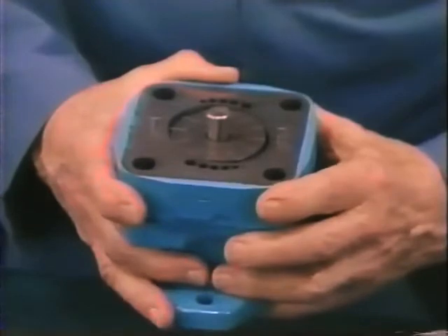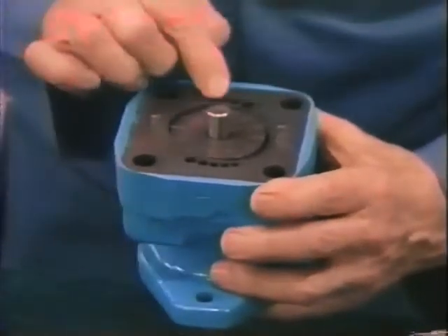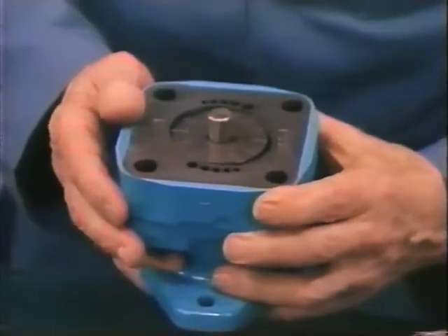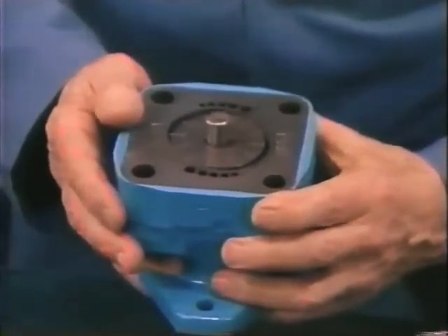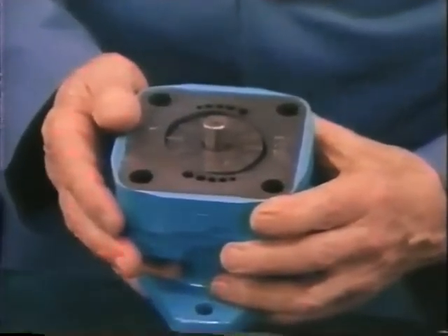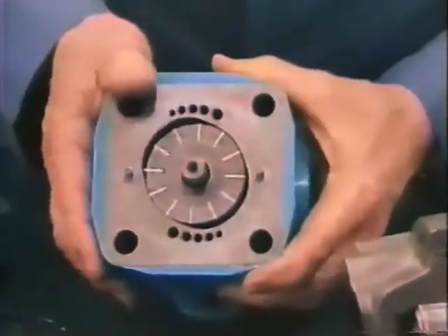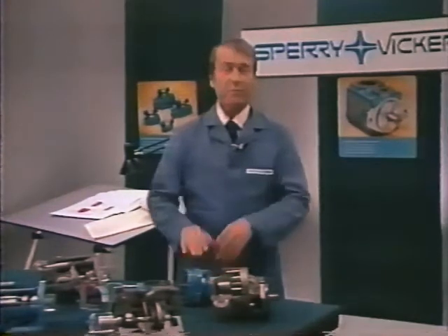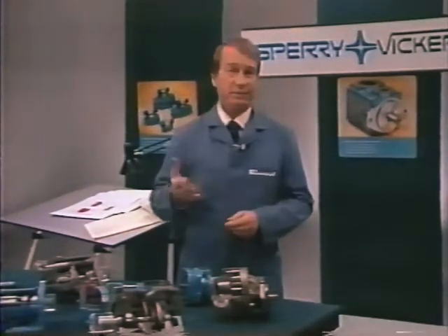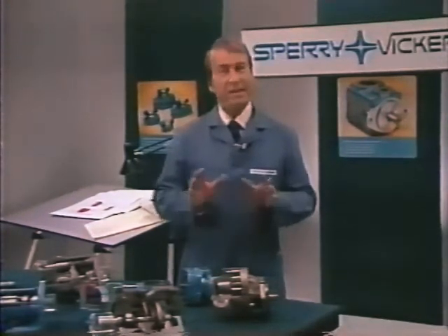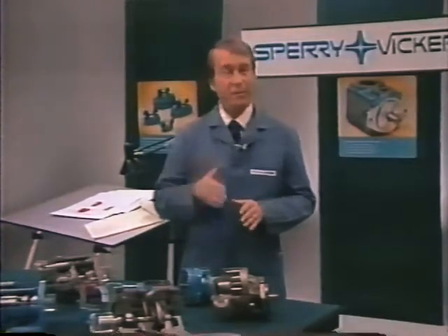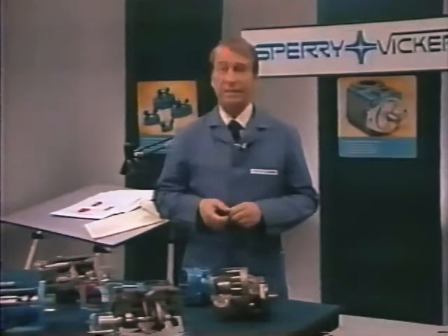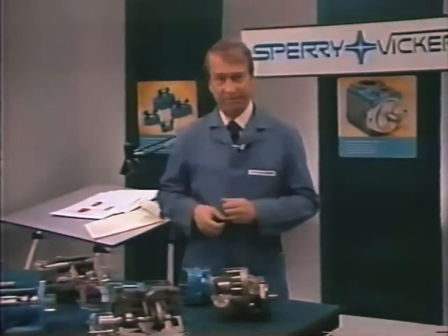The varying sized holes in the ring are called underpass holes. They improve pump inlet conditions by permitting oil to flow into the cartridge from both the body and the pressure plate side. Reassembling the pump is equally simple. With pressure plate loading being a function of system pressure, it's only necessary to tighten the cover bolts to their specified torque. But don't forget the little spring and O-ring seals.